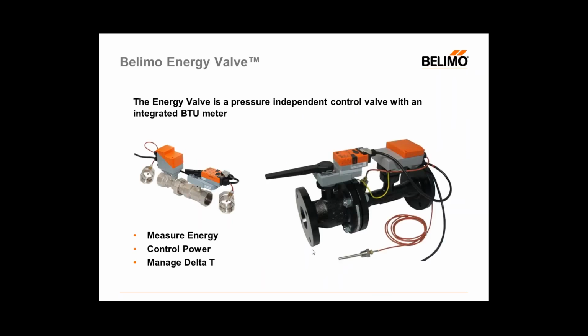So let's get started. What is the BELIMO energy valve? If you're completely new to this product, the BELIMO energy valve is an electronically pressure-independent control valve, and it has an integrated BTU meter in it. And what this allows us to do, a handful of things. Obviously, with a BTU meter in place, we're able to measure energy and get a much more precise read on what's happening at whatever piece of equipment we put this valve on, so our air handlers or fan coils or heat exchangers or what have you. It also allows us to be pressure independent or temperature independent using either flow control or power control. We'll have a webinar later this year that delves more deeply into those two features.